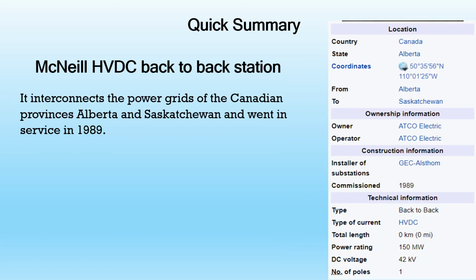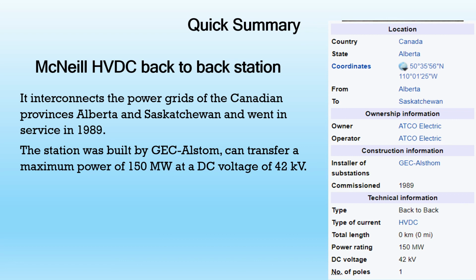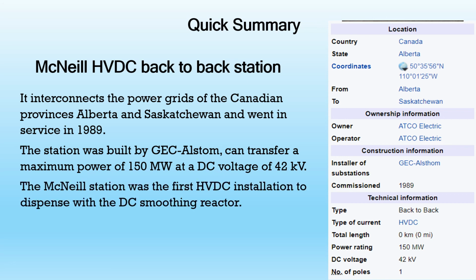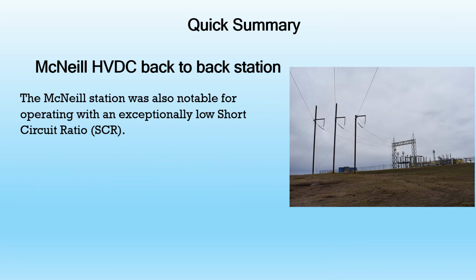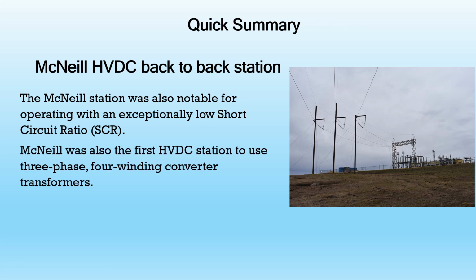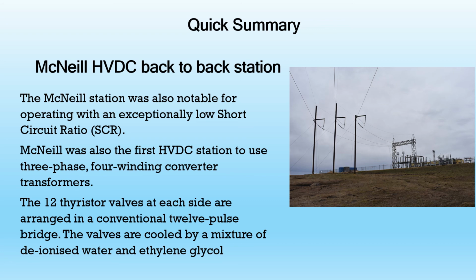Then we saw the McNeill HVDC back-to-back station, which interconnects the power grids of the Canadian provinces Alberta and Saskatchewan and went into service in 1989. The station was built by GEC Alstom and can transfer a maximum power of 150 MW at a DC voltage of 42 kV. The McNeill station was the first HVDC installation to dispense with the DC smoothing reactor. It was also notable for operating with an exceptionally low short-circuit ratio. McNeill was also the first HVDC to use three-phase 4-winding converter transformers. The 12 thyristor valves at each side are arranged in a conventional 12-pulse bridge. The valves are cooled by a mixture of deionized water and ethylene glycol.